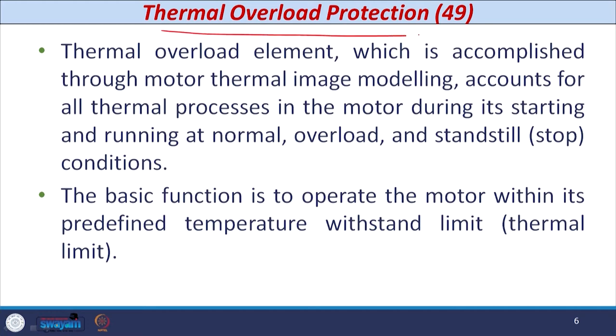Let us start with thermal overload protection. The number given to the thermal overload relay is 49. The thermal overload element is accomplished by modeling or image modeling of the motor, and it is accountable for all thermal processes in the induction motor — whether starting, running in normal condition, running in overload condition, or in standstill condition. The basic function is to operate the motor within its prescribed temperature limit, known as the thermal limit of the motor.